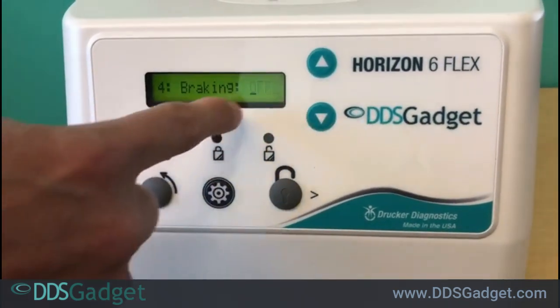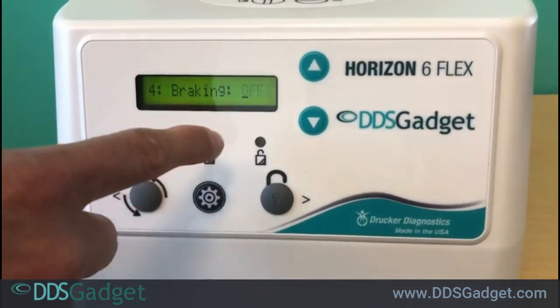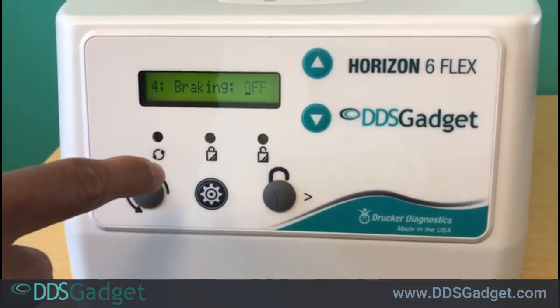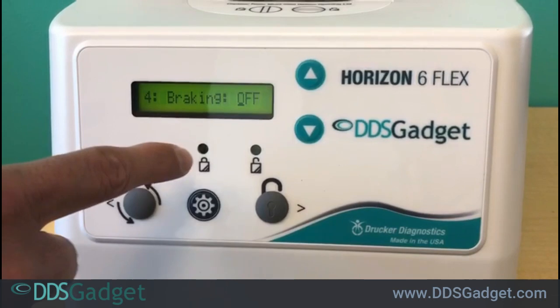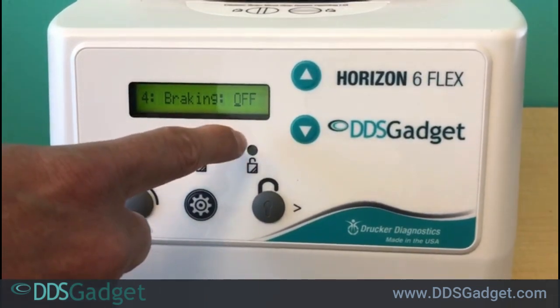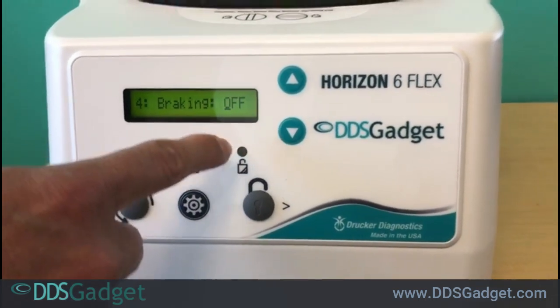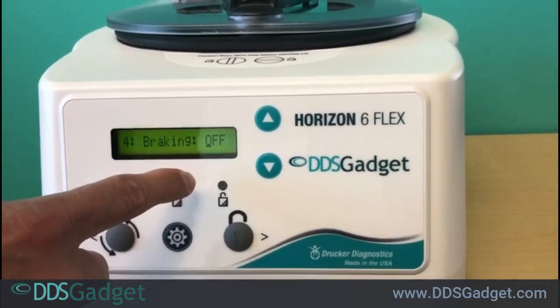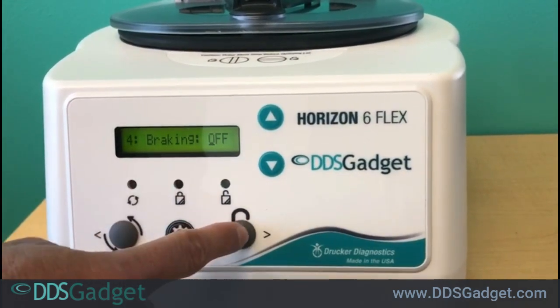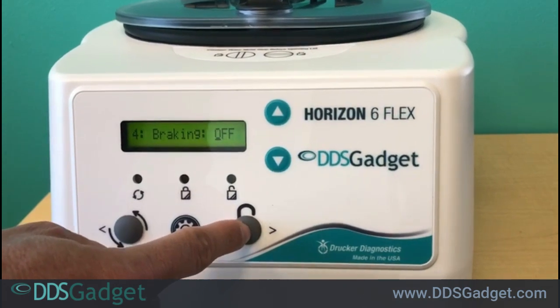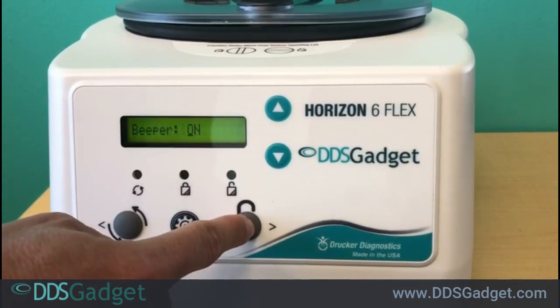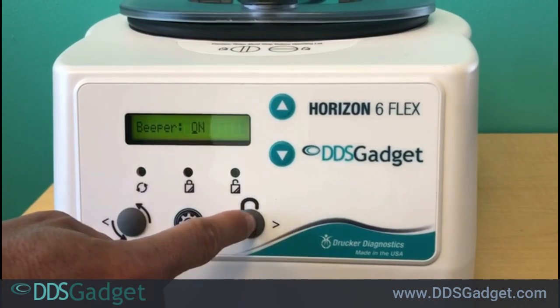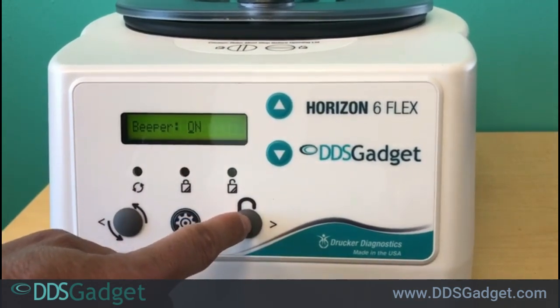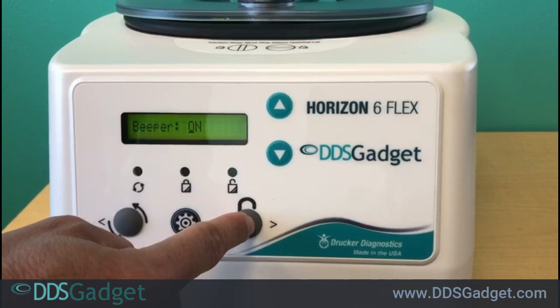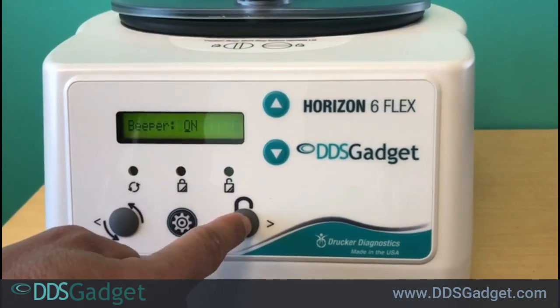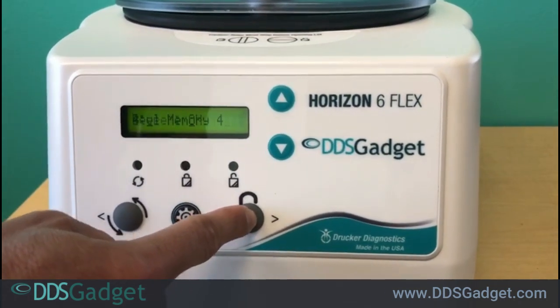It's best to leave braking off on the machine right now, and that's what we recommend. Braking is just how quickly it brakes once the cycle is done. And again, for dental applications, it's best to just leave the braking off, and the machine will cool down pretty quickly after the cycle is done, and you just open it once it beeps. So we'll turn braking off. Beeper we want to leave on. The beeper is that when the cycle ends, it beeps and tells you that the cycle ended. That's important. It's just helpful for knowing when you can come back to the machine.